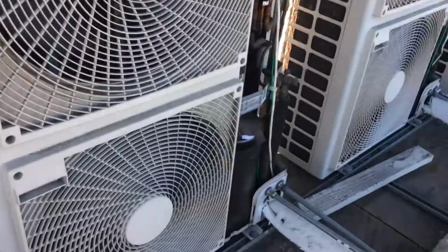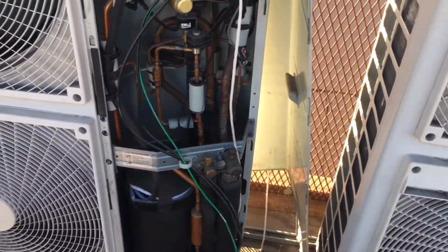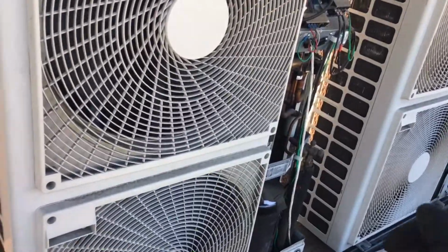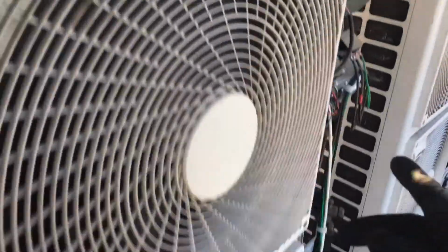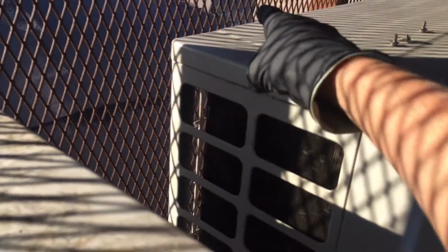I think I made a video on this once before, and yeah, I think when my son was out here servicing and cleaning, because this was the place where over here they have an outlet for a spray booth for an automotive shop, and out of that duct over there, different color paint comes out, and the fumes and the dust from the paint clog these condensers because the wind blows in this direction right into the back of all these and clogs up these condensers.